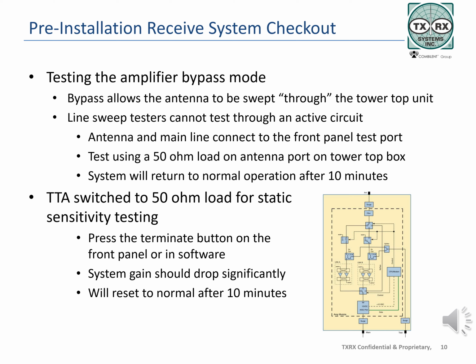Line sweeping is a test that allows transmission lines and the antenna to be tested on the tower after installation. The piece of test equipment used is called a frequency domain reflectometer, and it cannot see through an active circuit or a split in the transmission path, both of which the TTA represent. Bypassing the tower top unit reroutes the signal path around the amplifiers and puts the main line and the antenna in line with the test port on the front of the control unit.